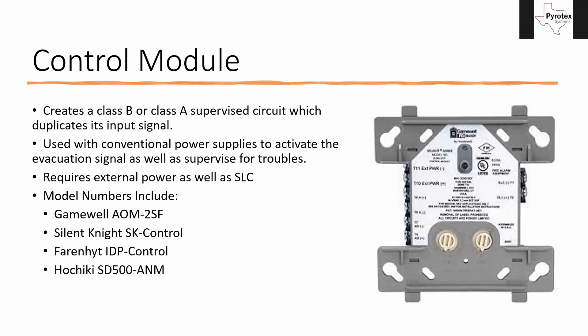We use these to trigger our conventional power supplies. We take auxiliary power off the power supply itself, run it into where it's labeled external power negative and external power positive. Then we come out of the Class B terminals at the bottom left-hand corner and go into the input trigger of the power supply. There's a spot to daisy chain the next signal or land your end-of-line resistor. This not only controls the power supply — we can program over the SLC to tell it when to turn on and off in a more intelligent fashion.